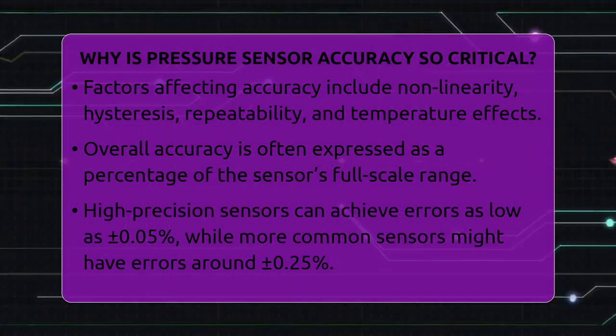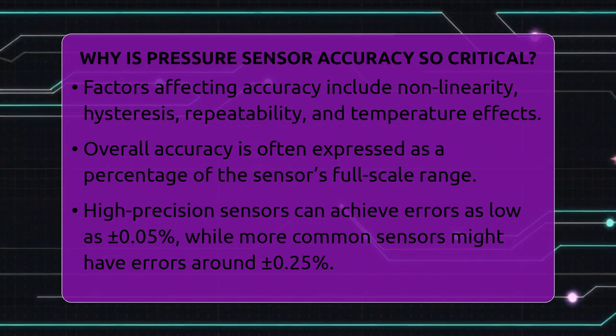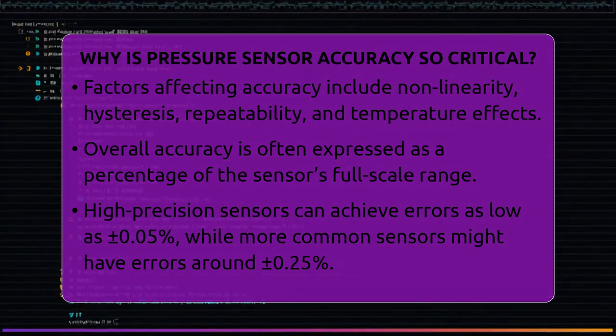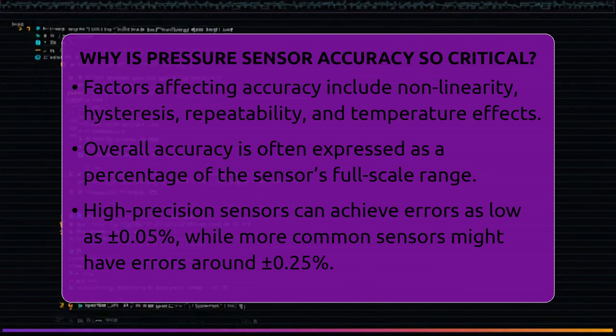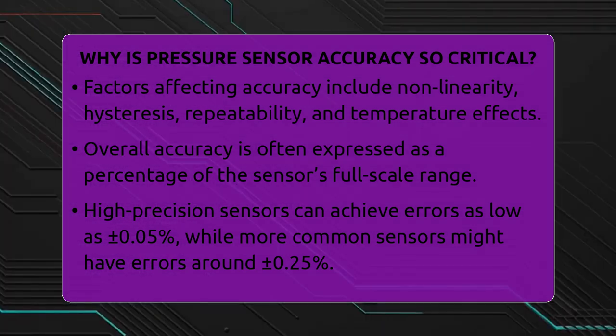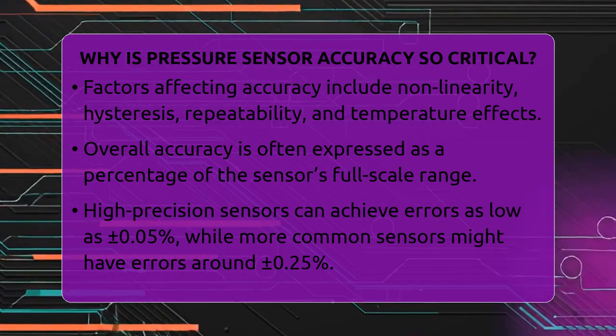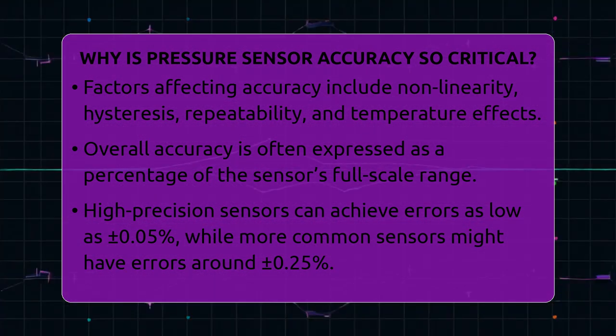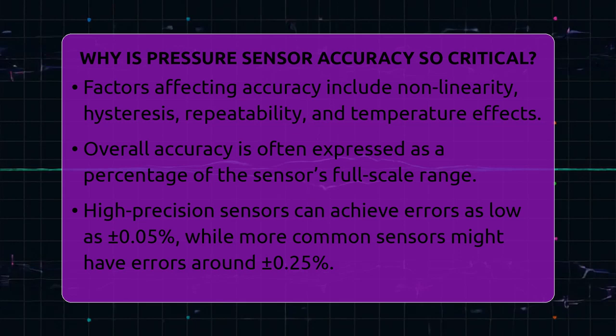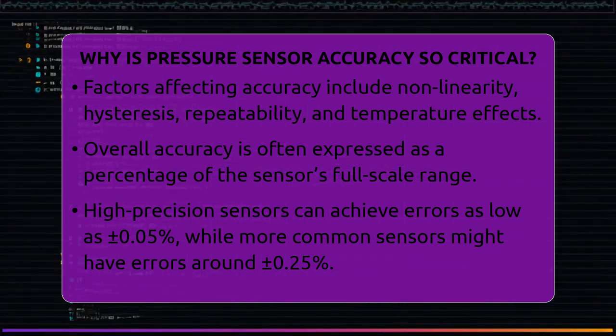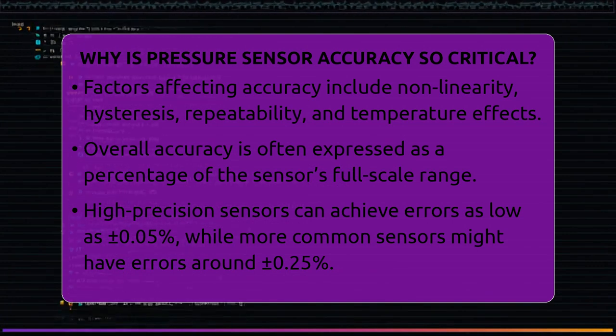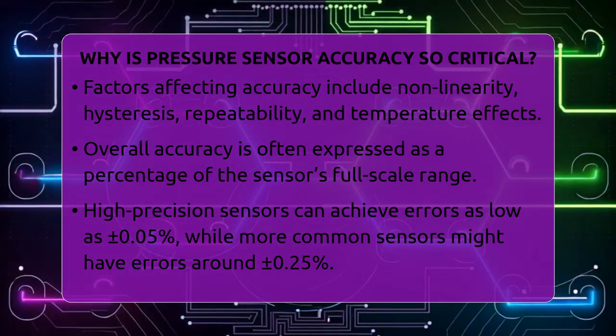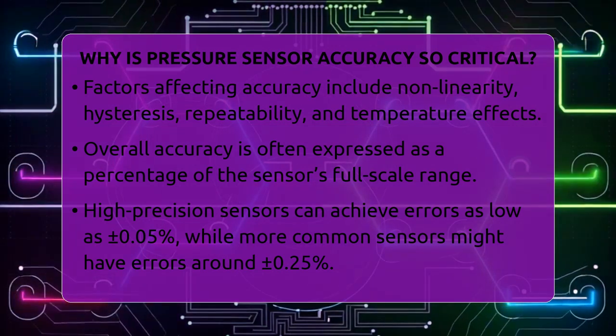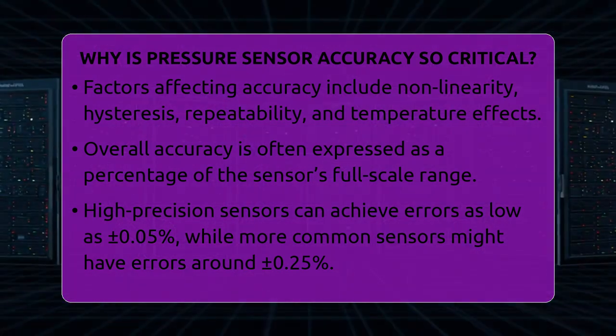These factors are combined mathematically to give an overall accuracy figure, often expressed as a percentage of the sensor's full-scale range. For example, a sensor with a 100 psi range and a 0.5% full-scale accuracy could have an error of up to half a psi at any pressure point. High-end sensors can achieve accuracy levels of plus or minus 0.05% of full scale. More common industrial sensors might have errors of plus or minus 0.25% of full scale.